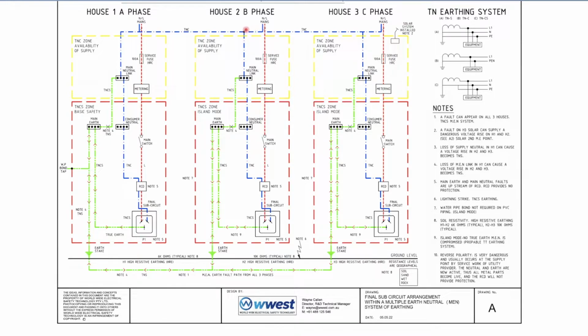But you take the neutral, and you can see across the top, this is the transformer link. At the transformer, the TNC is linked all the way between the three houses, straight across there like that. You can see how they're all linked back, whereas the actives, because they're on different phases, are separated. In this one, we've got the yellow zone. This is house 2 on B phase, and the yellow zone is exactly the same as house 1, and it's again availability of supply.